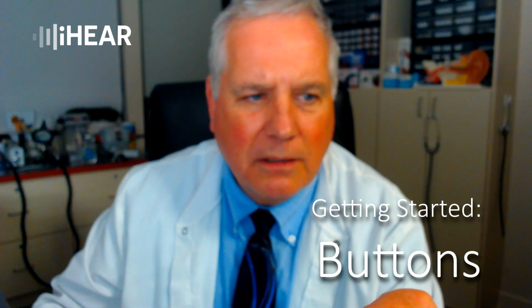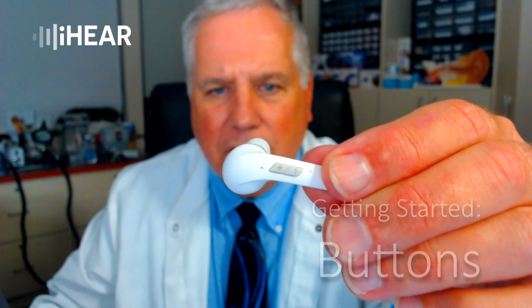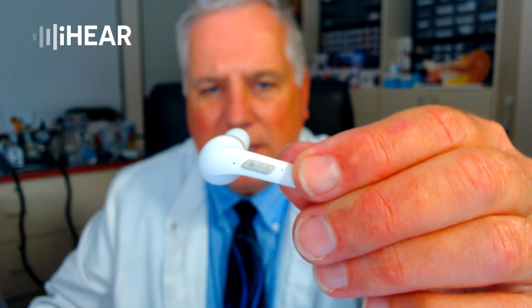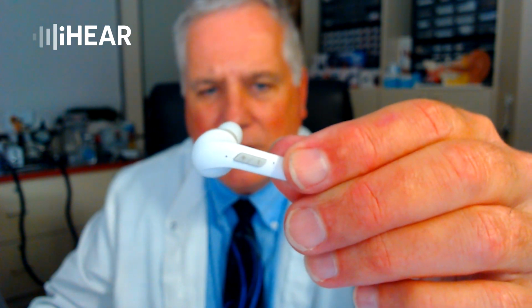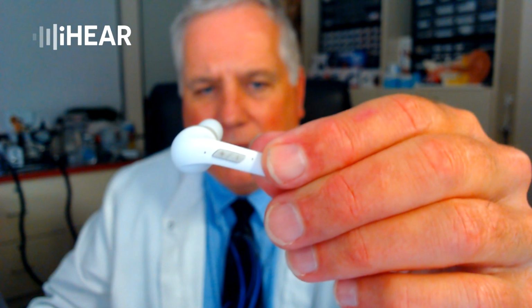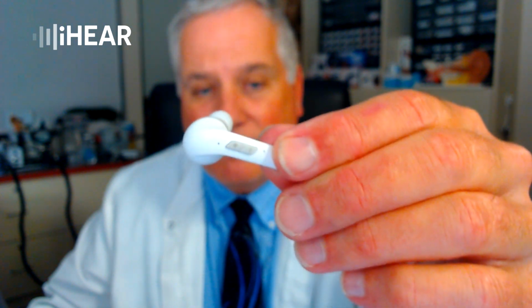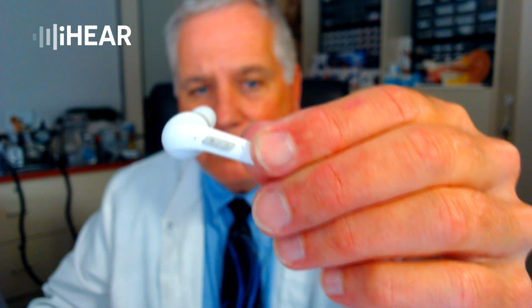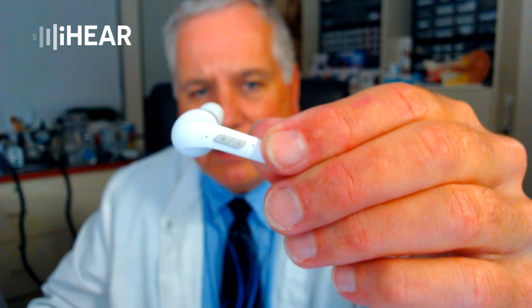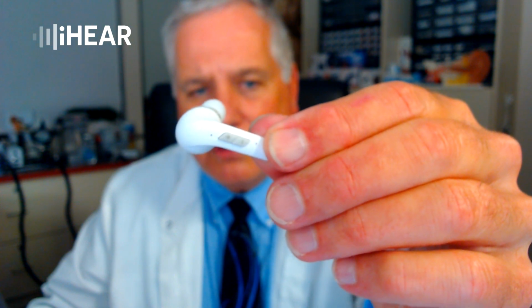I'm going to zoom in again. Okay, so let's see here. You're going to press and hold down that top button that has the plus on it, and if you hold that down for 3 seconds, you're going to hear either 1, 2, 3, or 4 beeps to indicate which program you're in. And that's how you change the programs. And then the bottom button and the top button, this is a multi-function button, so it'll change the programs. It will also change the volume. And when you press those buttons in and out real quick like a doorbell, it's going to change your volume up and down. Okay? So that is how you can change the volume and the programs on these hearing aids manually without having them connected to the phone app.